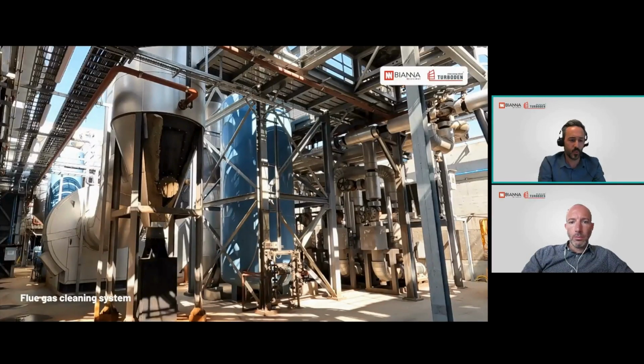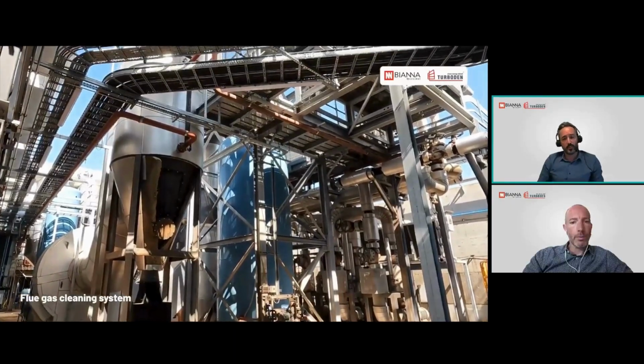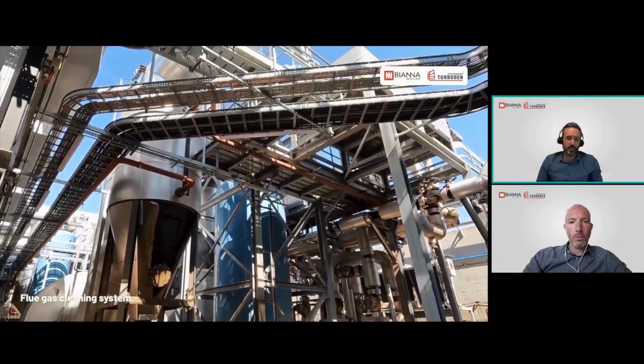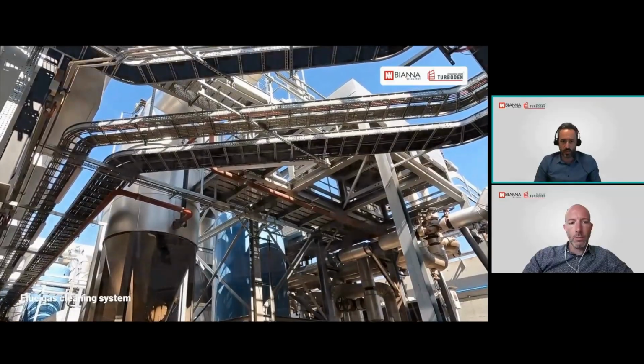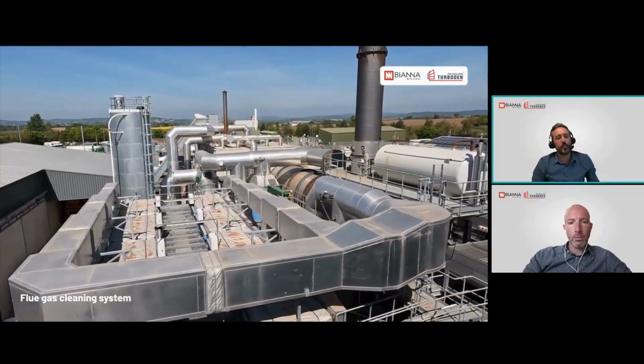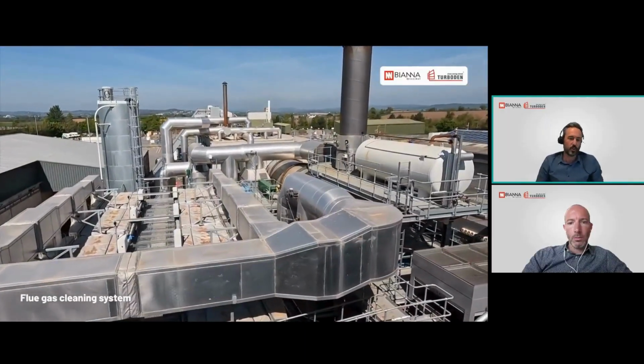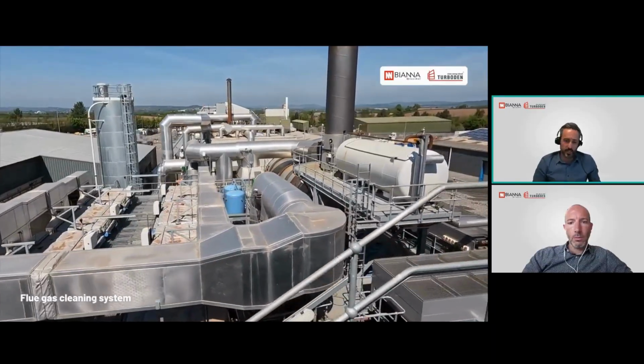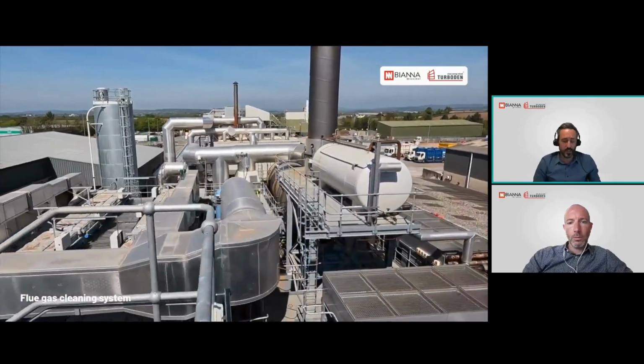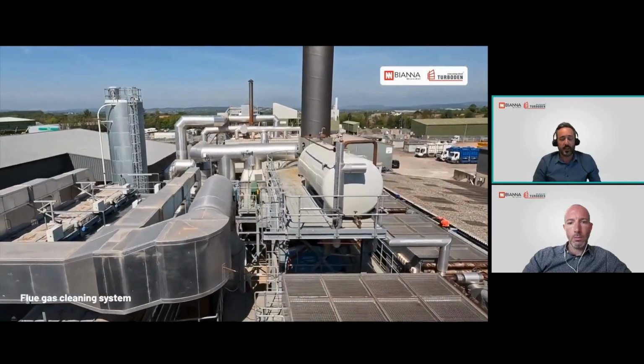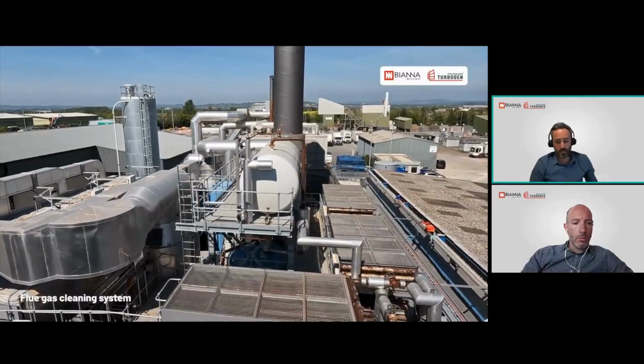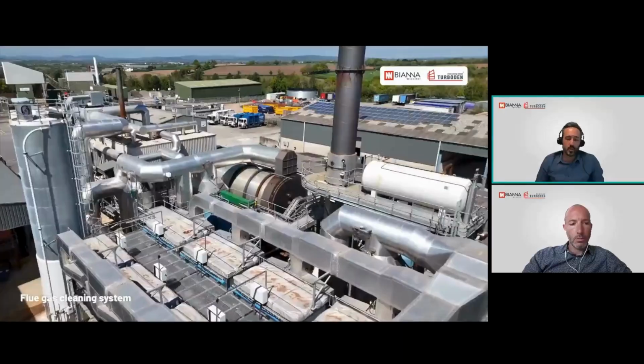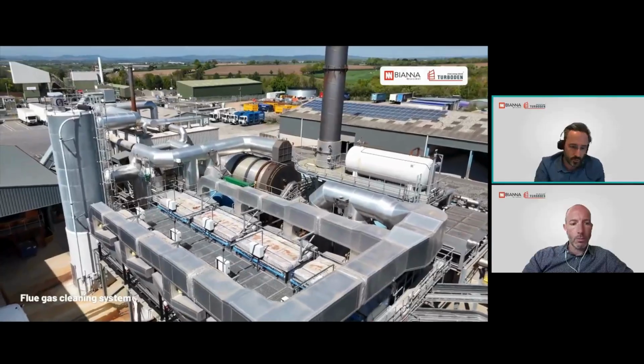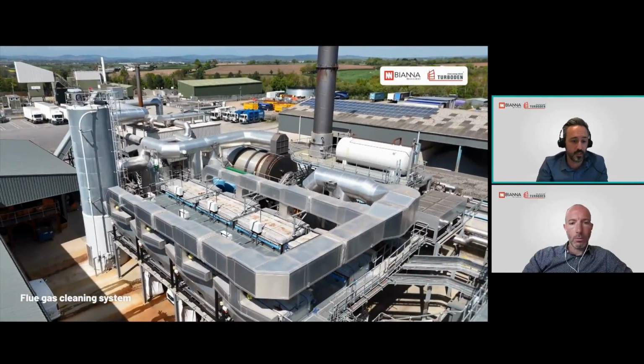Finally, regarding the supply in this site, we have the flue gas cleaning system. In this case, we have chosen a ceramic filter, which allows us to filter the particles that we still have in the combustion gases at that stage, under 5 milligrams per normal cubic meter at 6% reference oxygen. It's not only this, because this is a train of cleaning systems. We also inject calcium carbonate and limestone in order to remove acidic gases, heavy metals and VOCs, in order to meet the strict emission limits that we find in the UK and, of course, in the European Union.